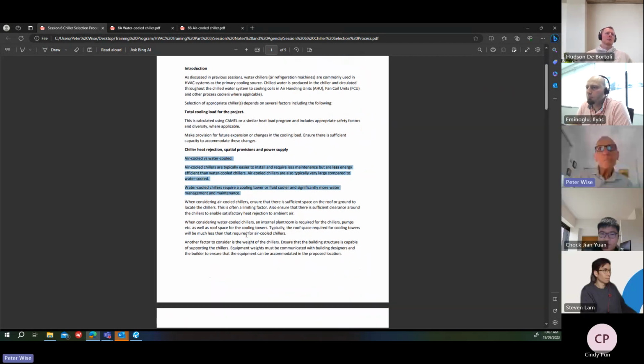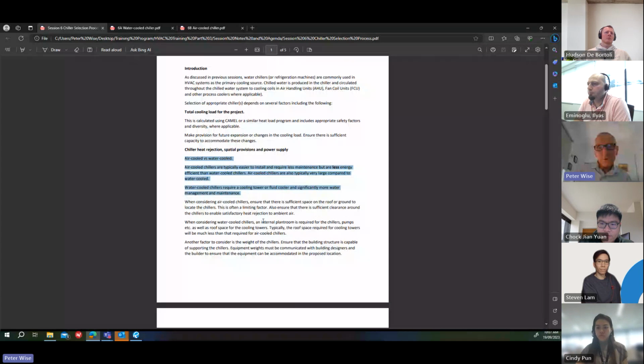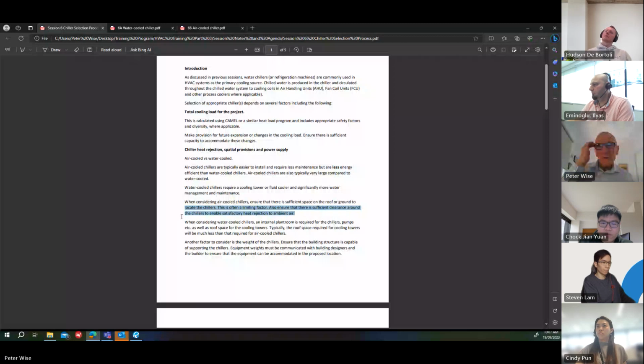When considering air-cooled chillers, ensure there's sufficient space on the roof or the ground to locate the chillers. So as I said, they can be very large, so you need a fair bit of space. And this is often a limiting factor. Also ensure that there's sufficient clearance around the chillers to enable satisfactory heat rejection to the ambient air. So the air's got to get in and out of the condenser to be able to reject the heat.